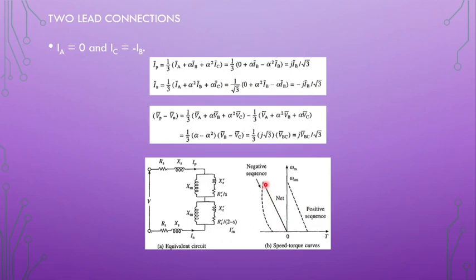So if the speed has to reduce, the torque will also reduce. And when the speed comes to 0, the torque will come to 0. So when the speed is coming to 0, torque is coming to 0 here. That is the advantage of this dynamic braking method. So if we just remove the connection of one of the phases in the loaded condition, if the load is very heavy, then slowly it will come to rest. Otherwise, it will run at a slower speed.